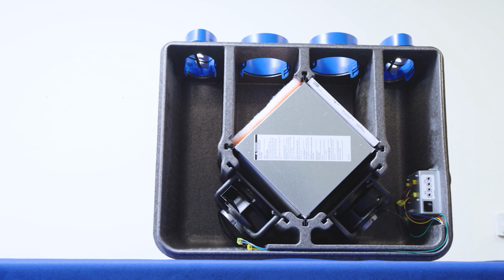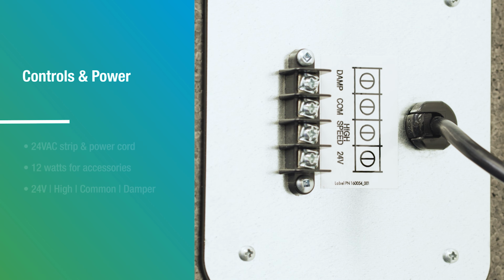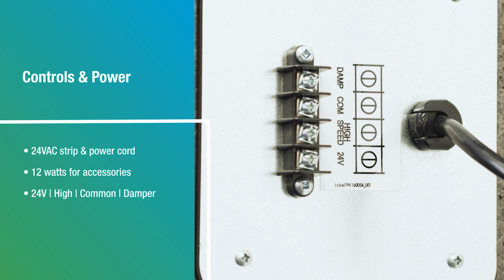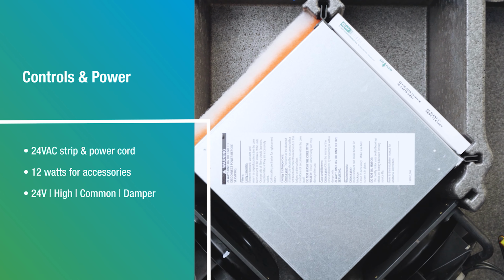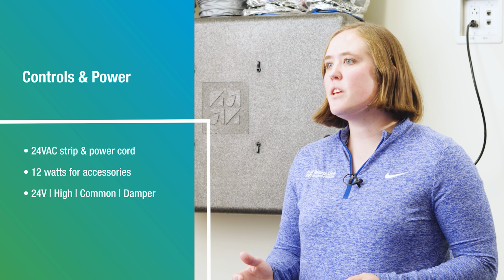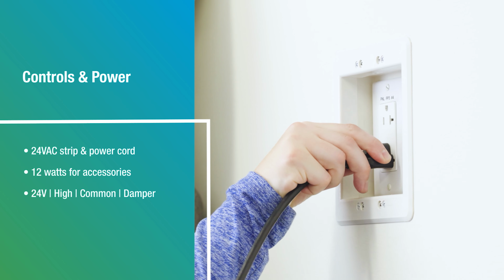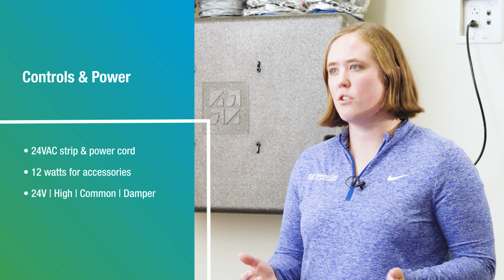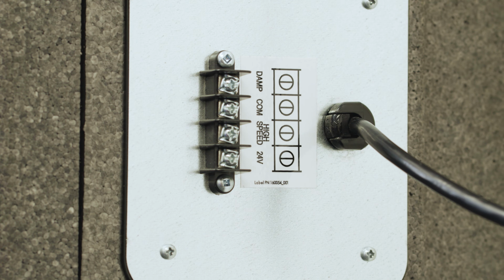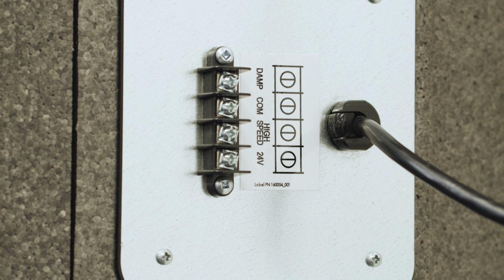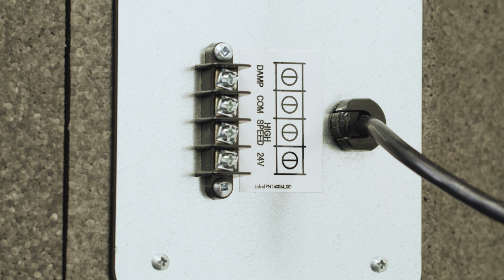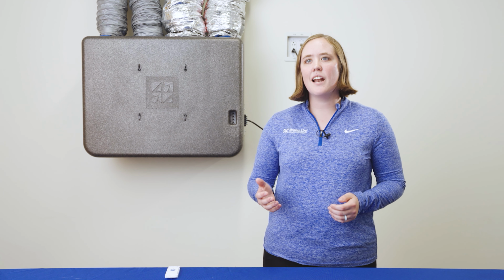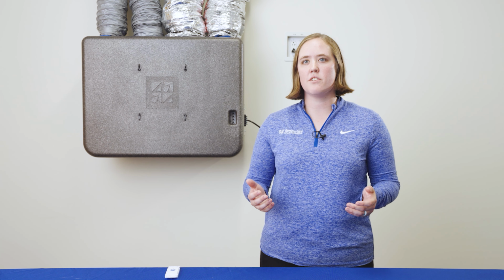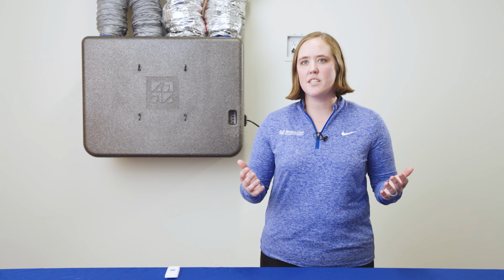On the right side of the unit, you will find the 24 volt AC controls terminal strip and the power line cord. The unit provides up to 12 watts to the terminal strip, which can be used to power the optional accessories like dampers, sensors, and controls. There are 4 terminals: 24 volt AC, high speed, also known as boost mode, common, and damper. Connecting the 24 volt AC and high speed terminals through a control accessory will activate the unit to run at high speed until the connection is broken.